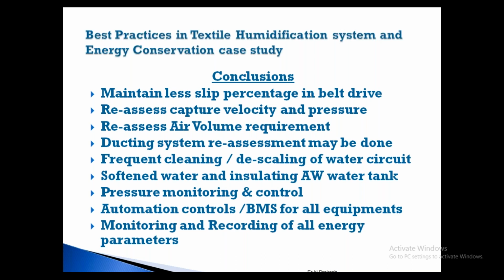So ducting system, revisit the ducting system, also very important. Duct insulation, all these things in an old plant, if you see, they put the duct and insulation very old. So that insulation material would have gone out. So without that, you will be exposing to the attic space, so temperature difference will be there. Whatever you run the plant, they will not switch off. They will not allow to change the frequency 50. Even that, we are not getting the RH like that. So we have to inspect. If you see, there will be a problem in insulation. Simple.